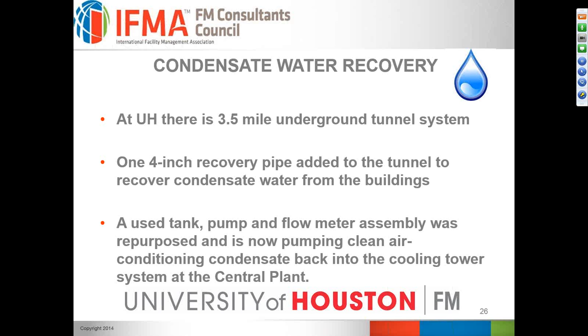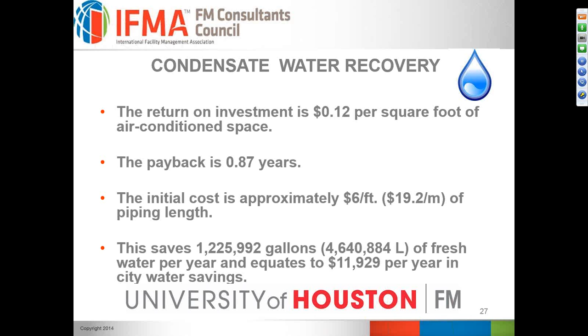Return on the investment is approximately 12 cents per square foot of air conditioned space. The payback for this initial installation is less than a year, and the initial cost was about $6 a foot in piping length. So far, we've saved about 1.25 million gallons of fresh water, which equates to about $11,000, almost $12,000 a year in city water savings.